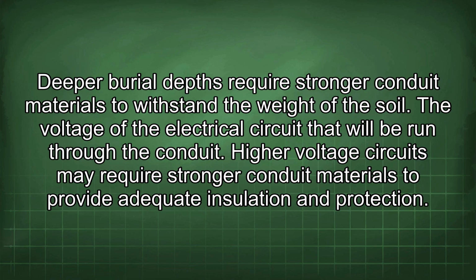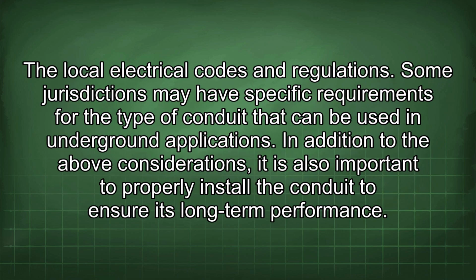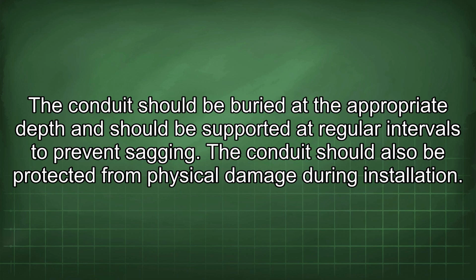The voltage of the electrical circuit that will be run through the conduit. Higher voltage circuits may require stronger conduit materials to provide adequate insulation and protection. The local electrical codes and regulations. Some jurisdictions may have specific requirements for the type of conduit that can be used in underground applications. In addition to the above considerations, it is also important to properly install the conduit to ensure its long-term performance. The conduit should be buried at the appropriate depth and should be supported at regular intervals to prevent sagging. The conduit should also be protected from physical damage during installation.